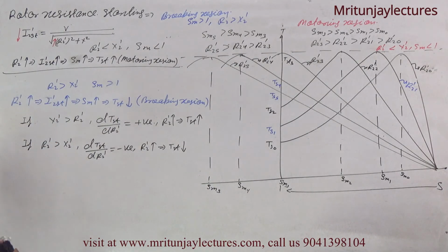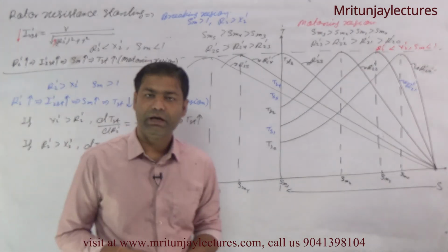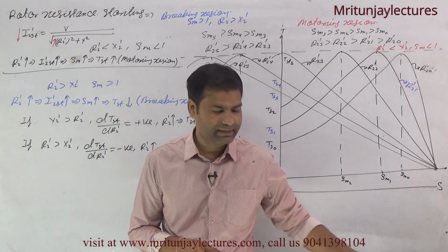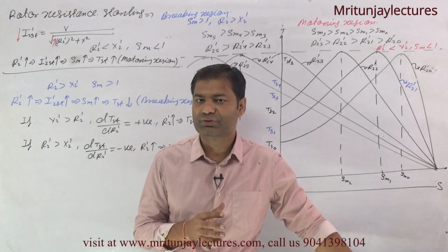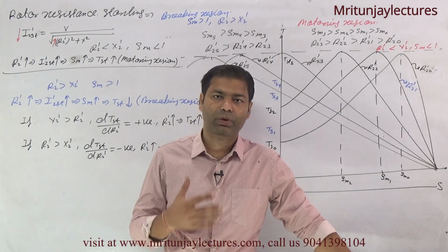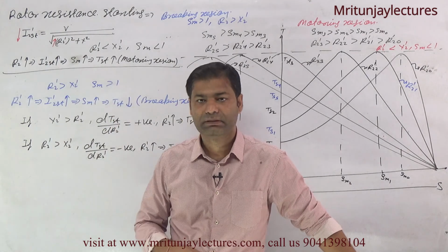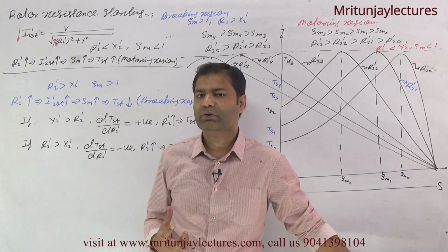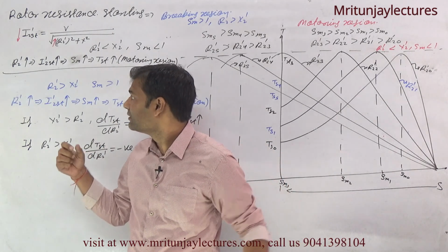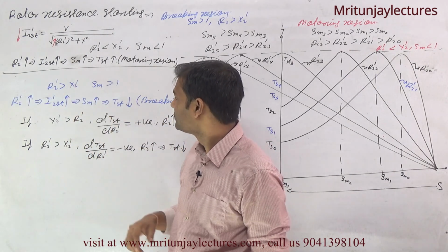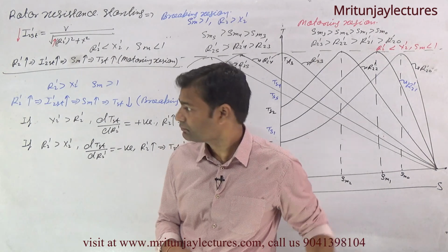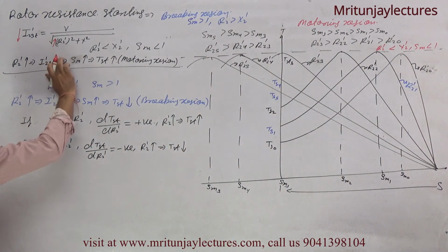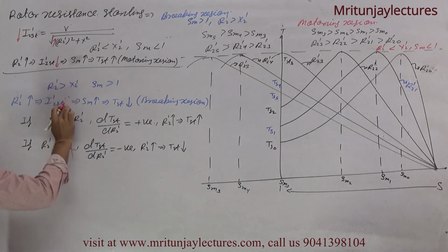Now finally, if external resistance is added in each rotor phase, then starting torque increases in the motoring region, and starting current decreases.